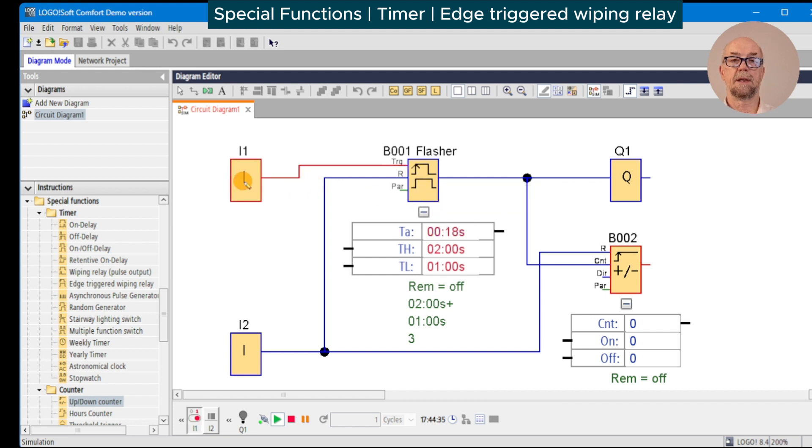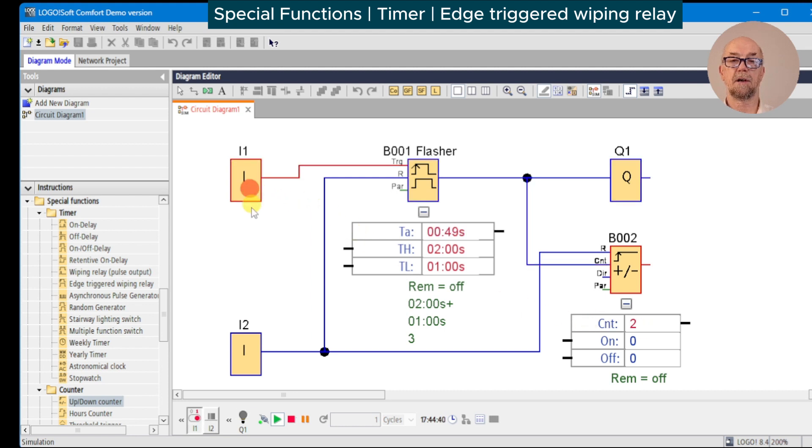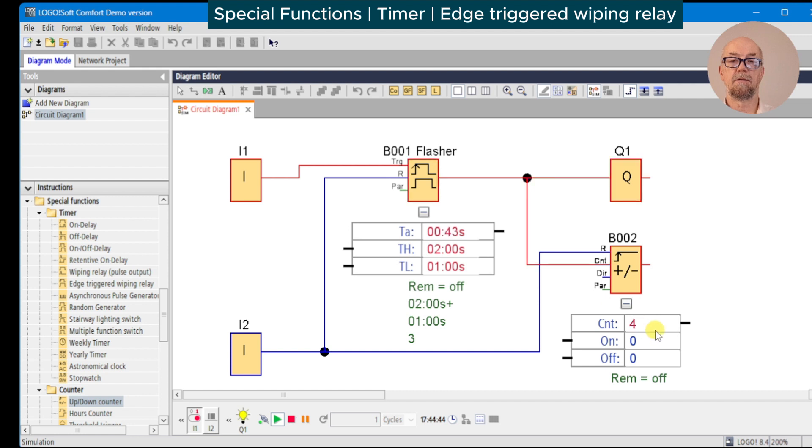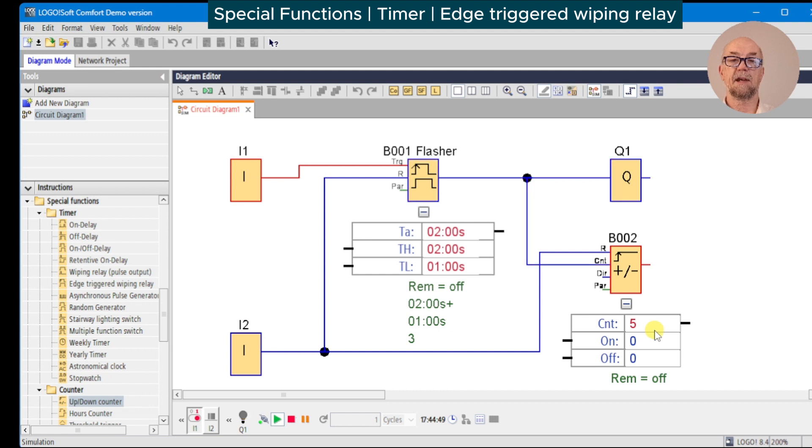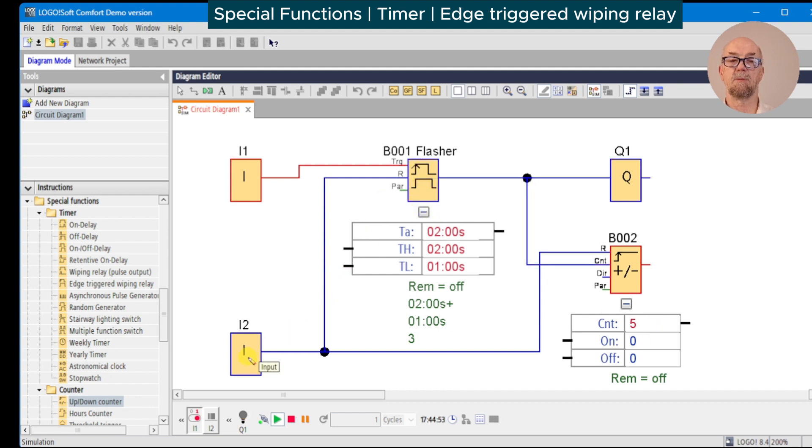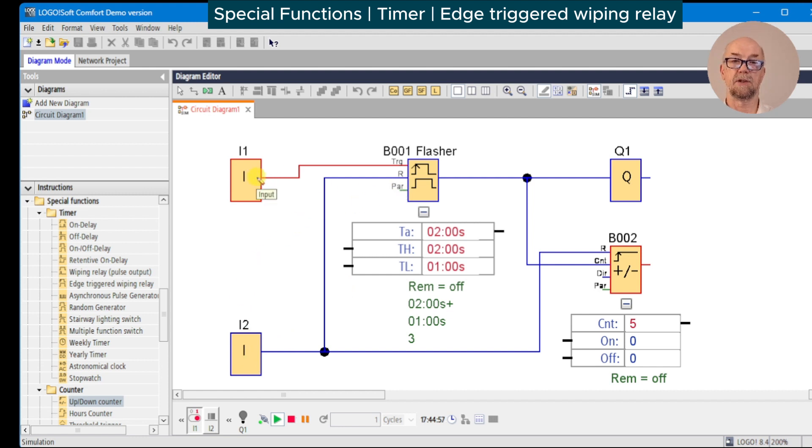We'll initiate again. Watch the counter: one, two, turn off and turn on again, and we get three, four, five. So the second edge trigger just reinitiates the sequence in much the same way as resetting the sequence and re-triggering would.